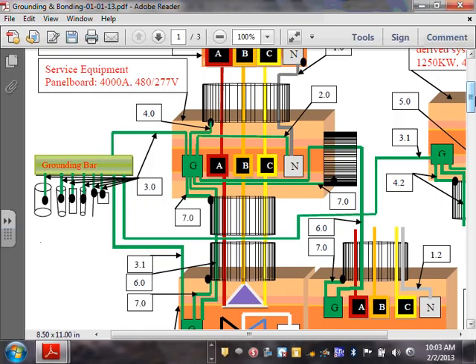So you group them all together to a bus bar, and you bring them to the switchgear. Now, can I bring them directly to the switchgear? Yes, you can. Why would this be a good idea to group them, guys? Because if you bring this one to the switchgear, what happens if you open the switchgear? Every time you open a switchgear, what do you need to do? Well, yeah. When you work in a switchgear, you have to put the switchgear in a safe working condition. Safe working condition is you lock it, you tag it.